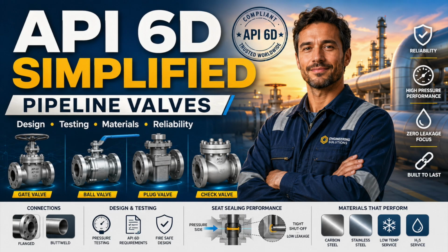Check valves are probably the most misunderstood automatic valves. Engineers often select them by size and pressure class. That is not enough. Check valve behavior depends on flow velocity, disc inertia, hinge geometry, orientation, reverse flow development, and transient conditions. The most important question is not whether the valve closes. The question is how it closes.